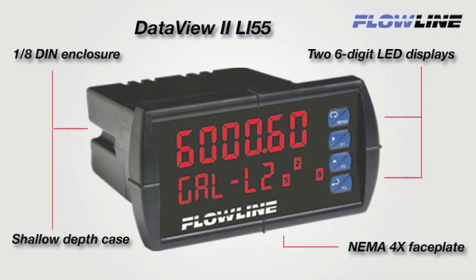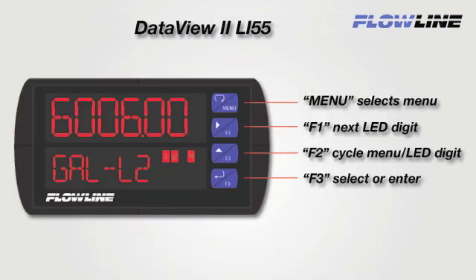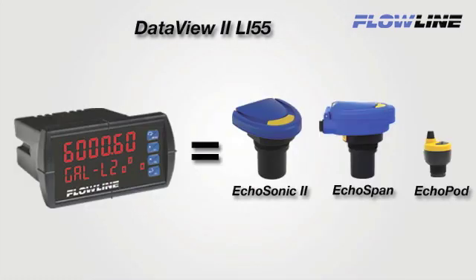First, let's get to know the DataView 2. The 1/8 DIN enclosure features a NEMA 4X faceplate and shallow depth case. The meter has a bright 6-digit LED main display and secondary unit display with relay status indicators. Four big and easy to access buttons allow configuration and control of the meter's features and programmable settings. The meter will work with any of Flowline's 4 to 20 milliamp analog output sensors like the EchoSonic 2, EchoSpan, or EchoPod series of sensors.